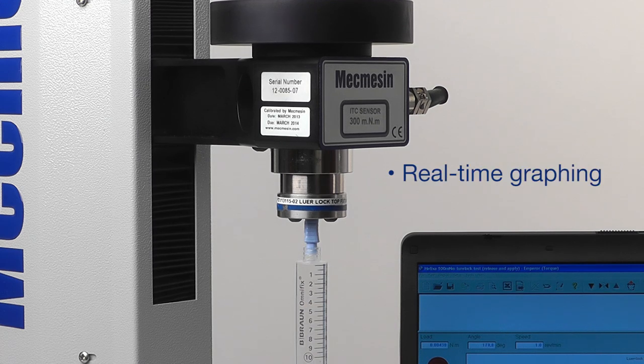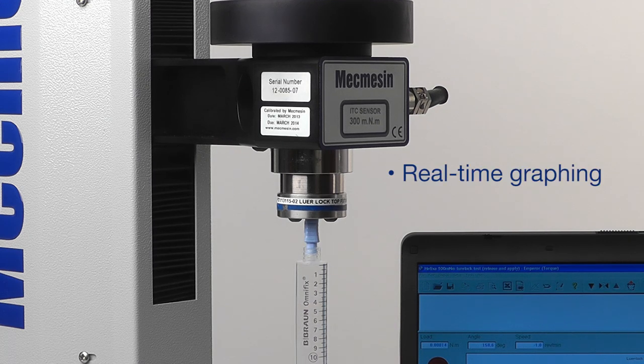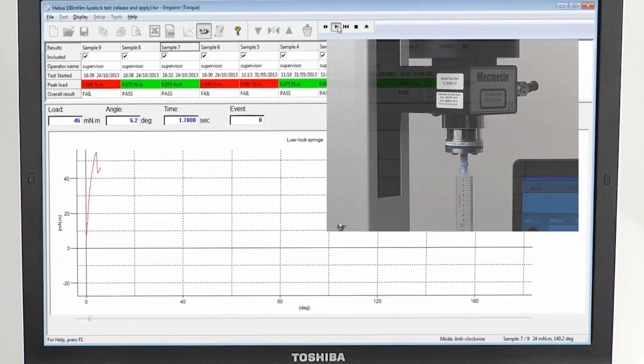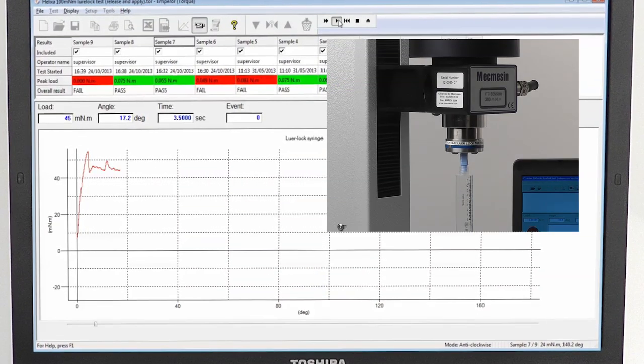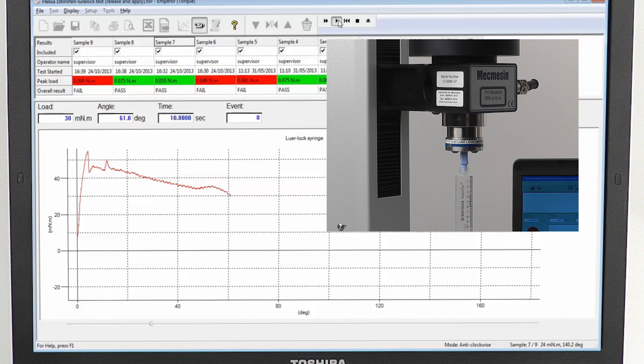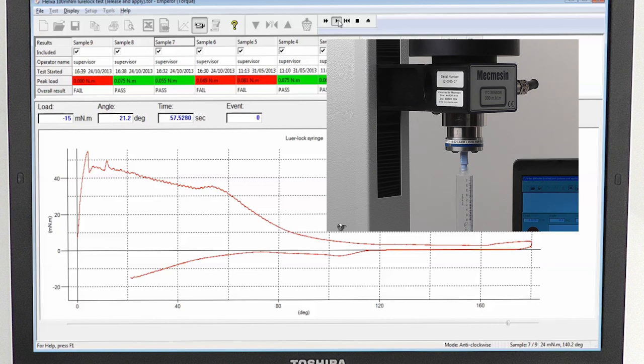The Helixa is controlled by Mecmesin's own Emperor software, which can be programmed to set the rotational speed from 0.1 to 30 RPM. Events are shown in real time, and you can set pass or fail criteria for the test, which are recorded in an unambiguous color-coded results display.